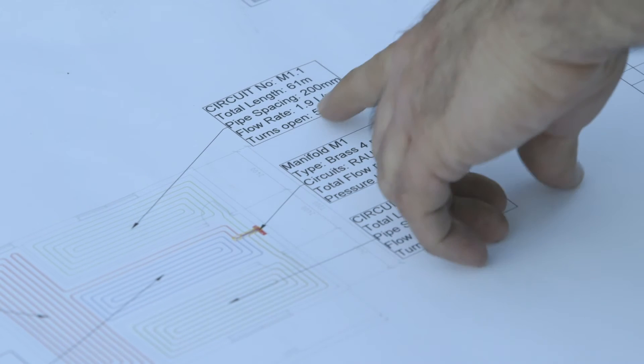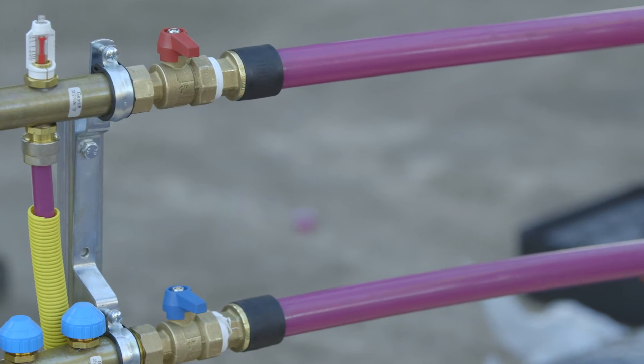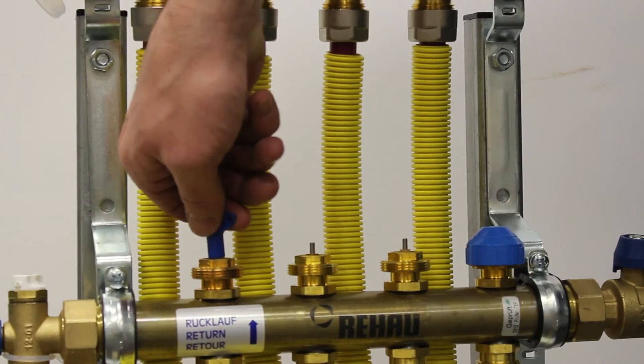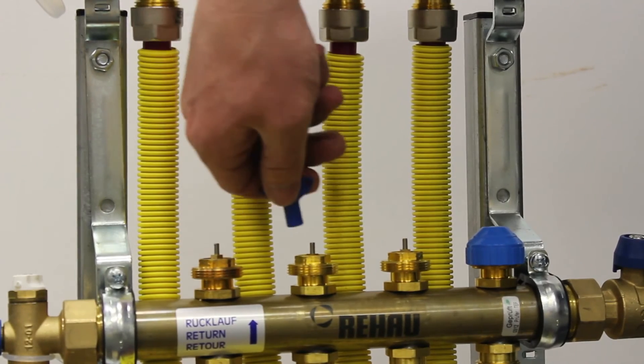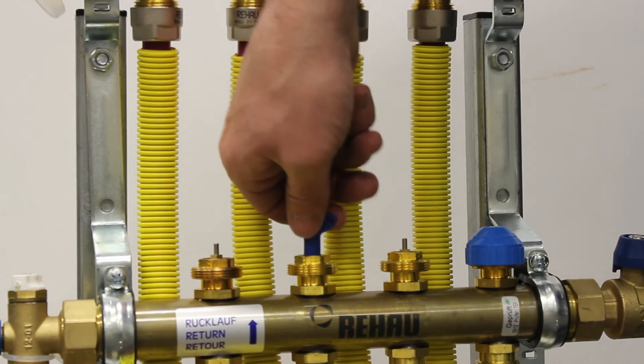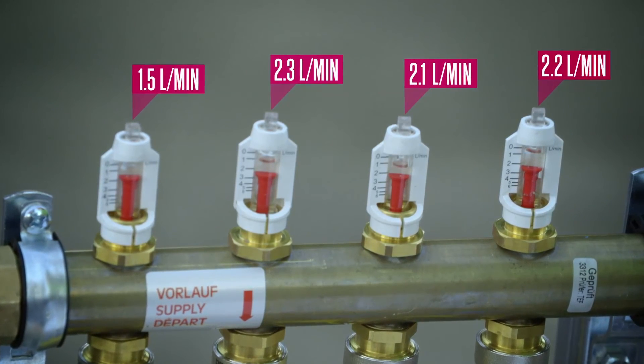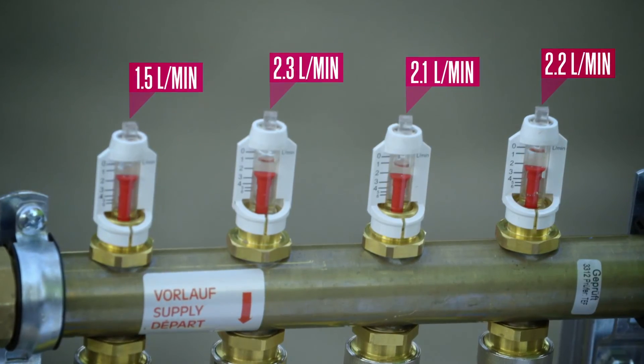Circuit balancing: once the system is operational, each circuit needs to be balanced to ensure consistent heat is applied to all areas. Using the Rehau design, follow the hydraulic balancing procedure on the design sheet by turning each control spindle the recommended number of turns. The control spindle is located under the blue cap on the return valve. Check the flow meters match what is recommended on the hydraulic balancing table and adjust accordingly.